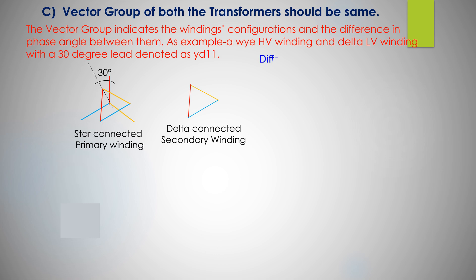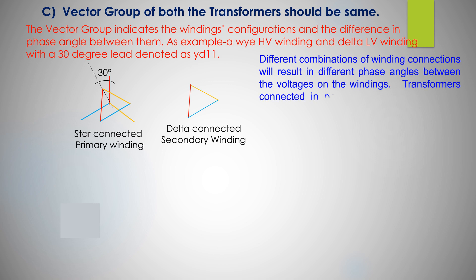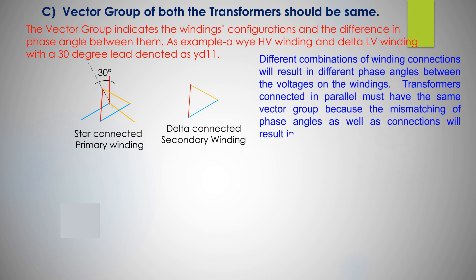Different combinations of winding connections will result in different phase angles between the voltages on the windings. Transformers connected in parallel must have the same vector group because the mismatching of phase angles as well as connections will result in circulating current and short circuit of system which have detrimental effect.